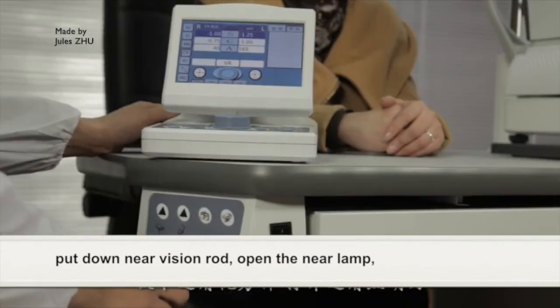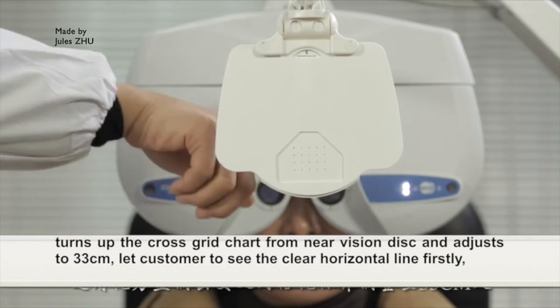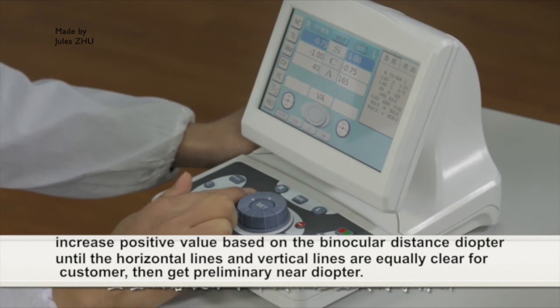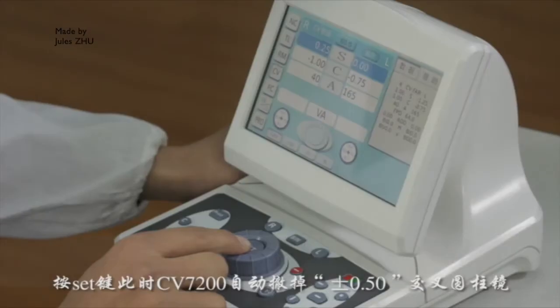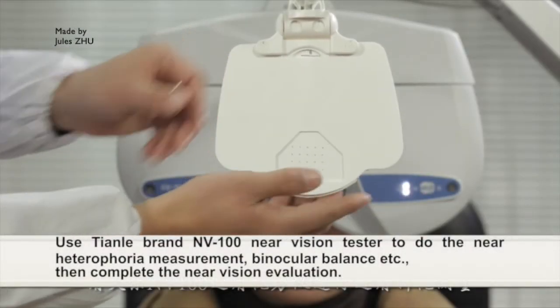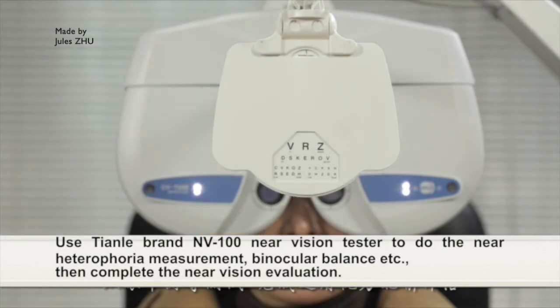Put down the near vision rod and open the near lamp. Turn up the cross grid chart from the near vision disc and adjust to 33 cm. Let the customer see the clear horizontal line first. Increase the positive value based on the binocular distance optometry result until the horizontal lines and vertical lines are equally clear for the customer. Then get the preliminary near optometry result. After pressing the SET button, this instrument removes the ±0.50D cross-cylinder automatically, then performs the NRA/PRA test for further fine-tuning of the presbyopia prescription. Near visual evaluation: use the NV100 near vision tester to do near heterophoria measurement, binocular balance, etc. Then complete the near vision evaluation.